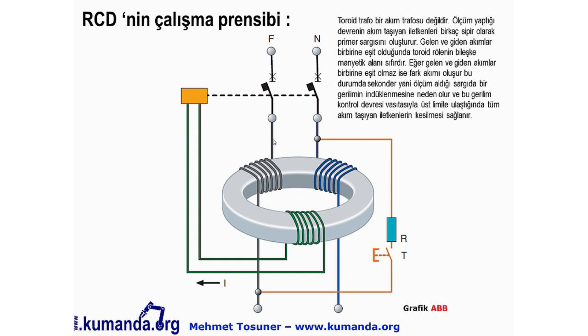İki kutuplu bir RCD'de faz ve nötr, toroid içerisinden geçtikten sonra çıkışlara verilir; sekonder sargıda ölçüm alınır. Normal şartlarda fazdan gelen ve nötrden dönen akımlar eşit olduğunda bileşke manyetik alan sıfırdır. Akımlar arasında fark oluştuğunda sekonder sargıda gerilim indüklenir; üst limitlere ulaştığında açtırma mekaniği tetiklenerek faz ve nötr iki kutuplu birlikte kesilir.